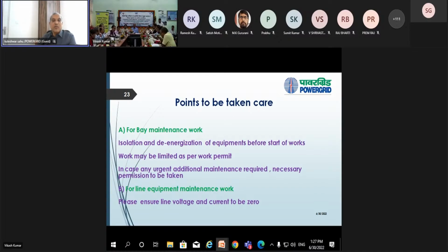We have seen several trippings, bus bar tripping. We are going for the annual maintenance of the bay equipment, and we thought there is some alignment issue with the isolators. So during the same time we went for alignment work, and there was a bus fault. So we should strictly adhere to what we have been allowed. Line equipment is connected with the lines, so please ensure line voltage and current are zero before earthing the system. That is very important.